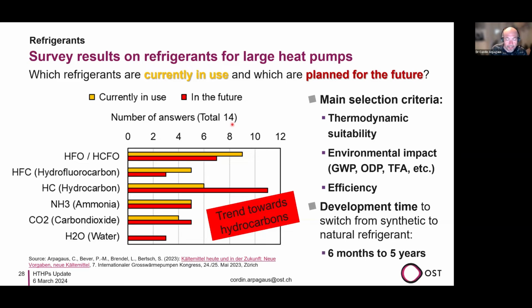And the main selection criteria for the refrigerants are: the thermodynamic suitability, so that the refrigerant works in the temperature range needed for evaporation and condensation in the heat pump cycle. Then we have the environmental aspects, so a refrigerant with no or very low global warming potential, that it has no ozone depletion potential because it's forbidden, then that it does not produce some other acids when released accidentally into the environment. And then efficiency in terms of COP, the advantage of heat pump technology.